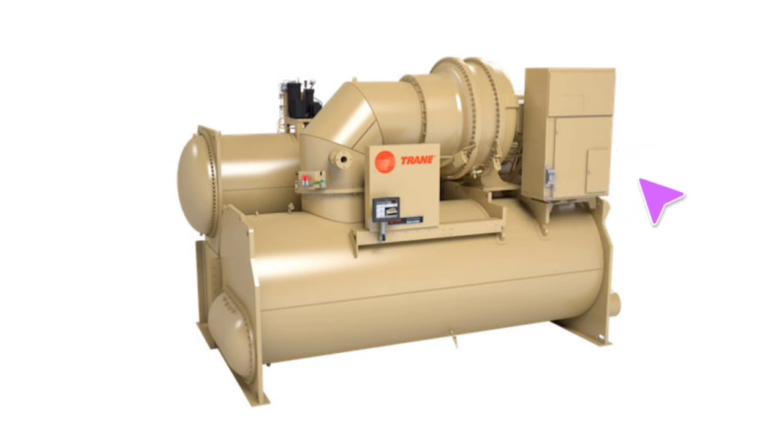So a lower lift is going to play less of a factor on a Trane centrifugal. The question comes up, okay, so what is too high of lift, what is too low? That's going to be purely dependent on that piece of equipment. Trane in my experience handles a lot higher lift than many other brands, largely because of the way they design their compressors with the multiple stages. They do really, really well, but what they don't do is they don't handle very low lift very well. So a York YK series handles low lift situations extremely well, but it does not perform well in high lift scenarios like the Trane can.